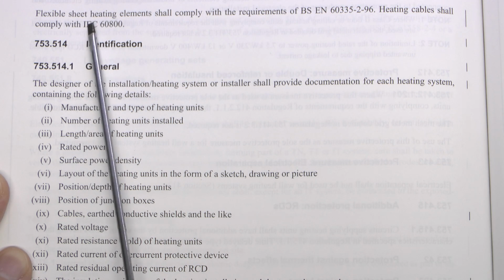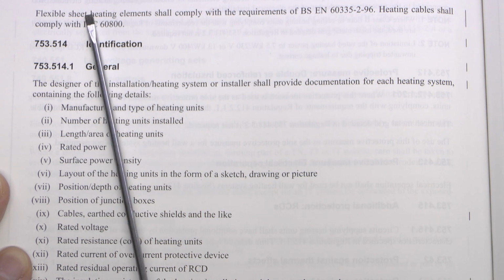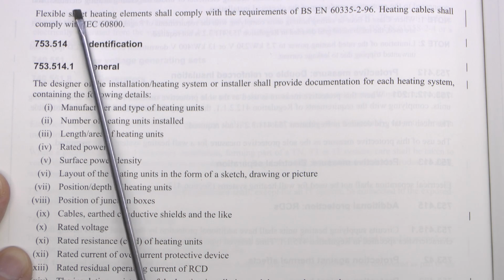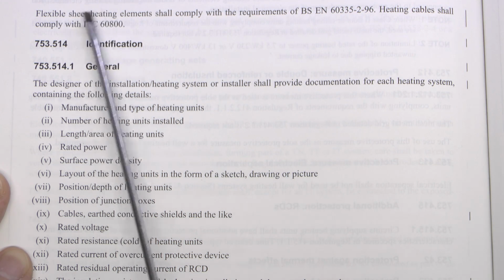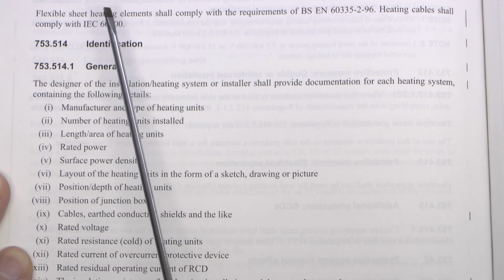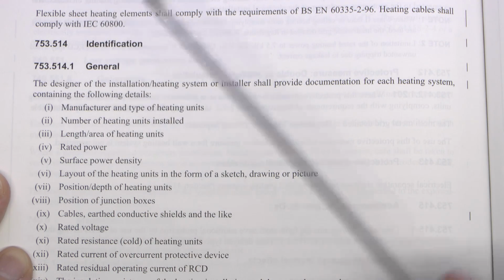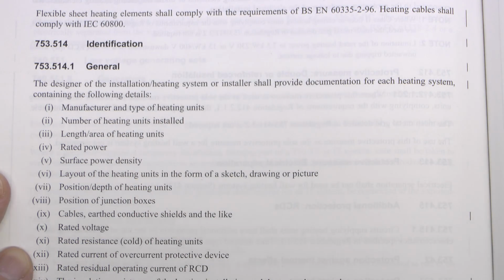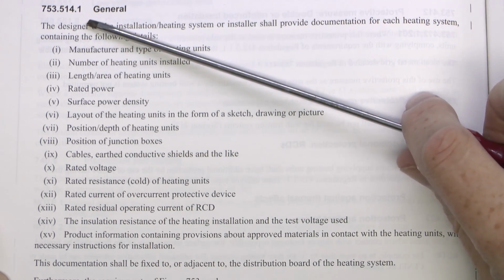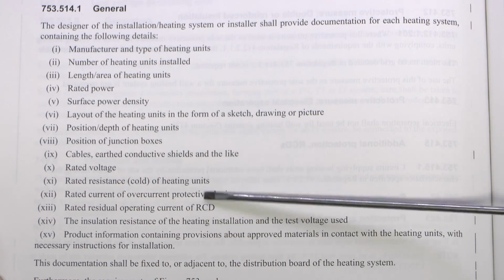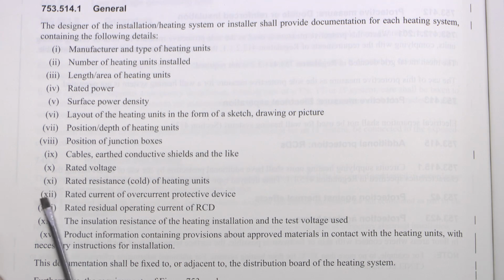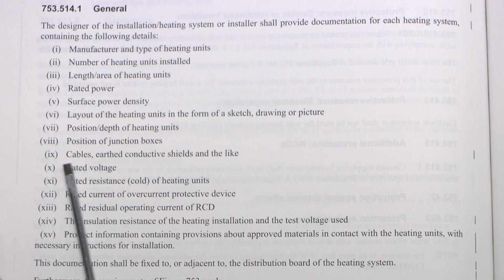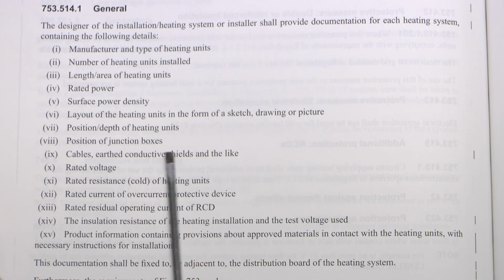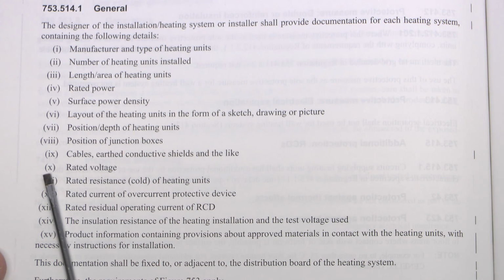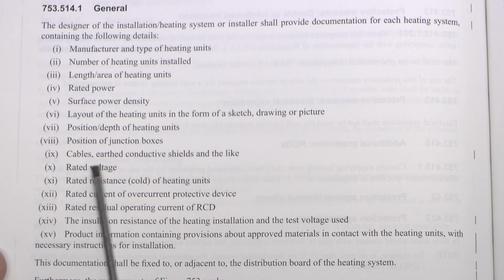There are a few bits that have been deleted here, which were 753512. There's actually 5121 and 5122. Those have basically been deleted, and they were about operational conditions and external influences, so those have been taken out. 753514, general, is substantially the same, and there are a couple of items that have been altered. The item here, which is now cables, previously had conductors, conductive shields and the like. There used to be a piece here about the heated area, that's been deleted. Leakage capacitance was here, and that's also been deleted.